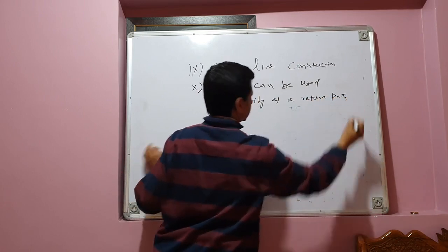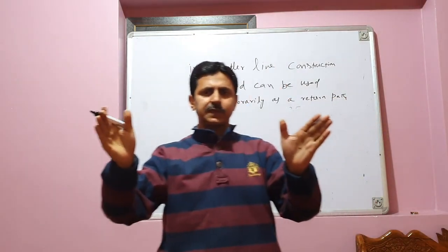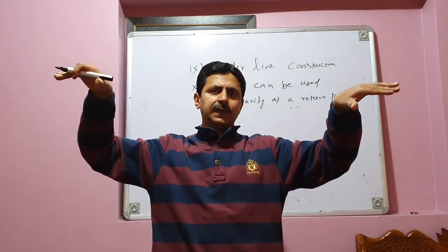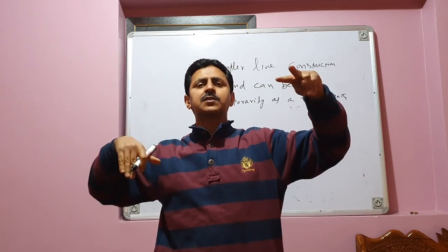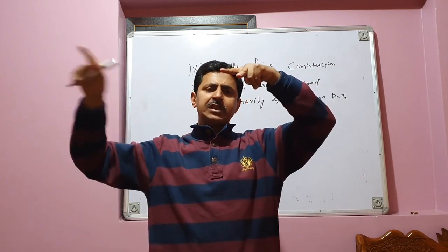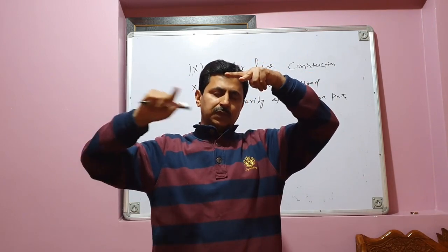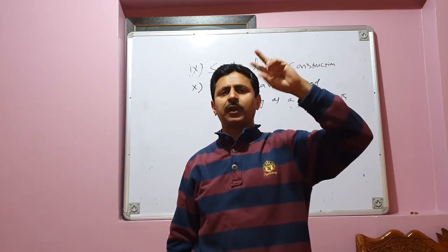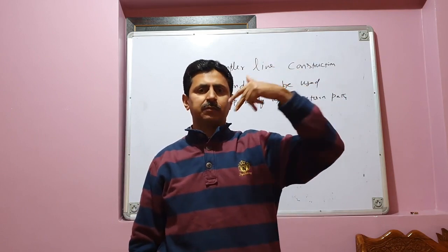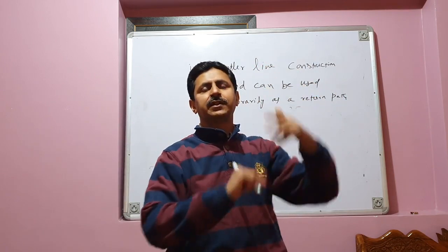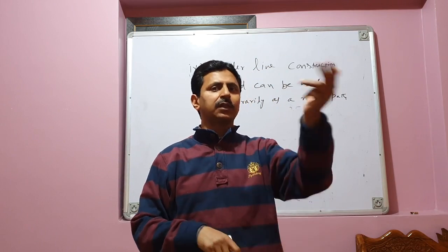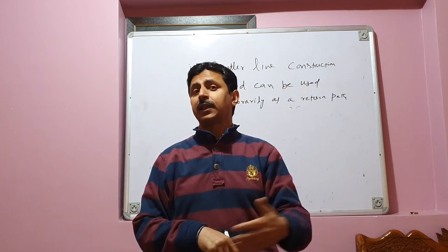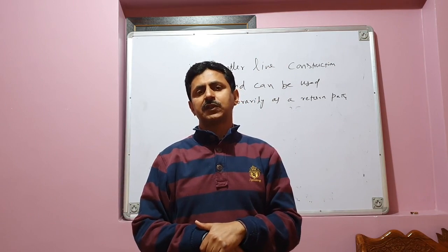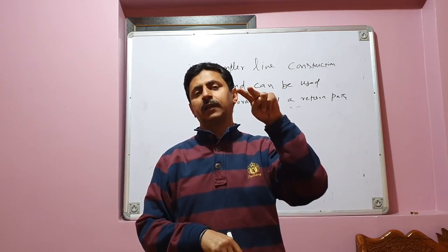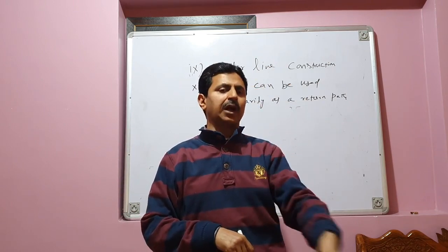So, for example, in an AC transmission system, how many lines do you require? 3 lines, 3-phase transmission. In DC transmission, you need only 2 lines, one positive, one negative. So sometimes if there is a fault with one of the poles, we call these lines poles, if one of the poles is dysfunctional because of a fault, you can use ground as a return path temporarily for some time till the fault is rectified. So this is another advantage with HVDC power transmission system. You need only 2 conductors, and in the event of a fault on one of the poles, you can use ground as a return path.